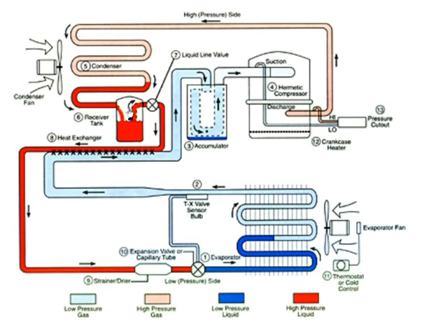Alright, and basically that's what subcooling is. So over here on the evaporator coil, we're heating the refrigerant because we've got hot air blowing through a cold coil. We're trying to get the heat out of the house. So we're taking that hot air and blowing it through a cold coil. As long as we know what the temperatures are, we can tell how well the system is working.